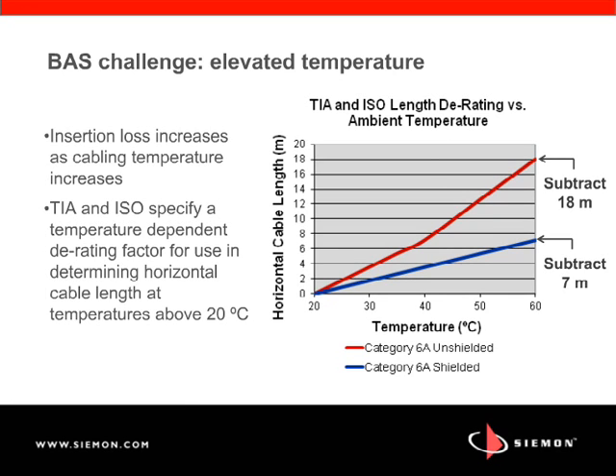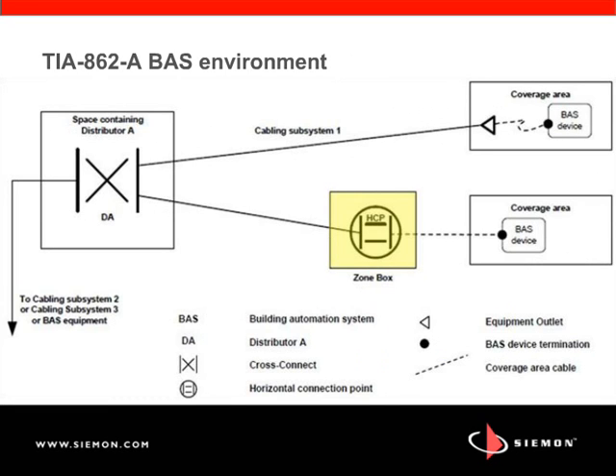I'd like to chat just a minute about deployment of BAS applications. According to TIA 862A, there's a couple different ways we can support device connections. We can support connections to telecommunications outlets directly from distributor A or the interconnect patch panel in the closet. There are also provisions for using a horizontal connection point that's enclosed within a zone box that can facilitate direct connections to the BAS device or connections to an equipment outlet that supports the BAS device. So there's lots of flexibility.